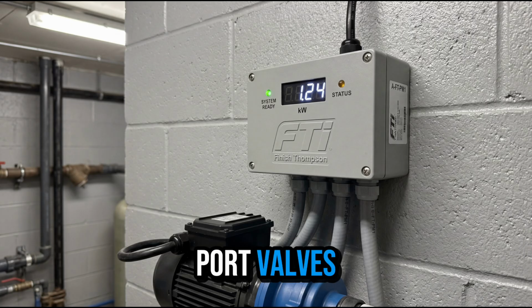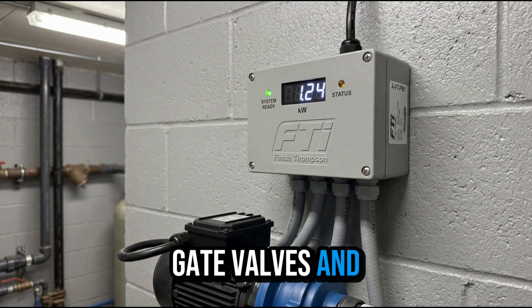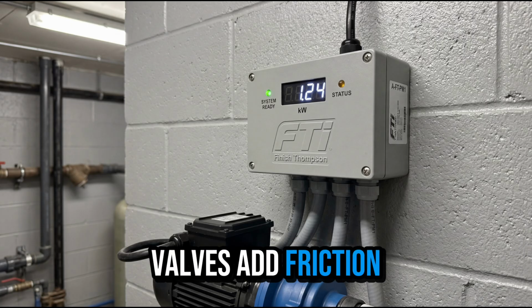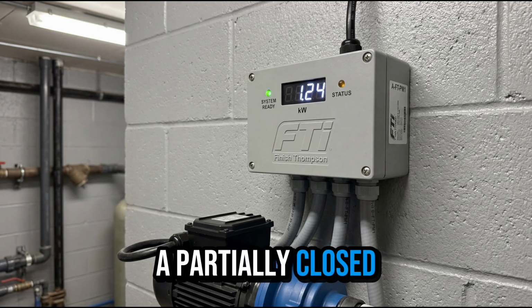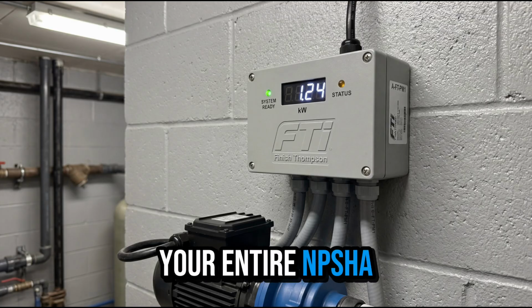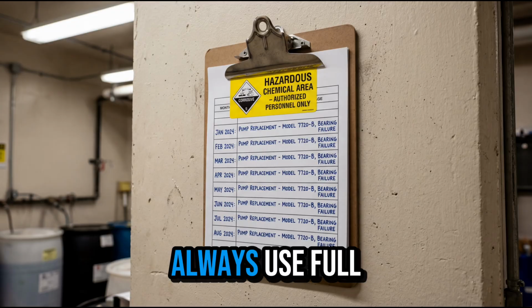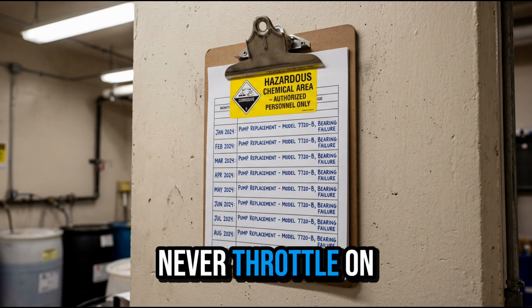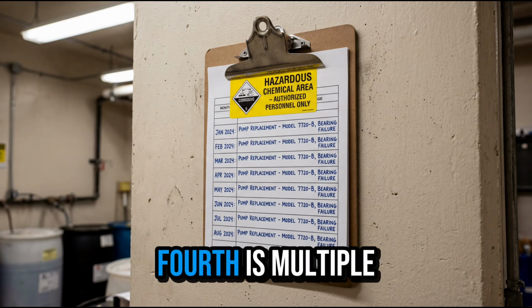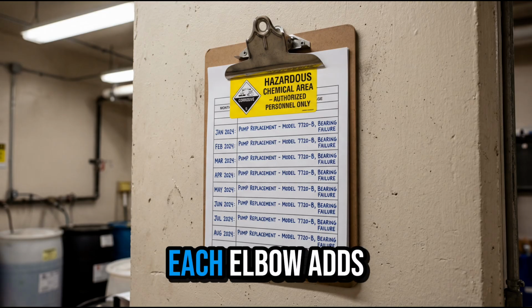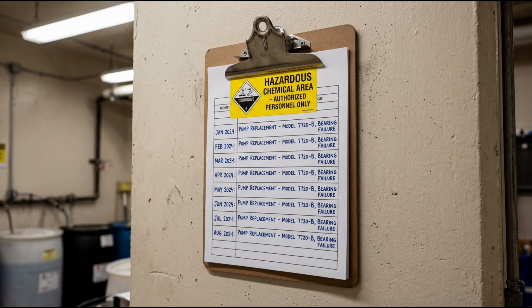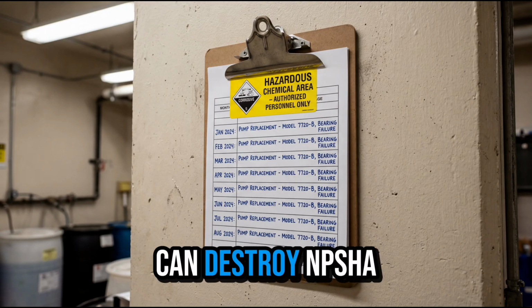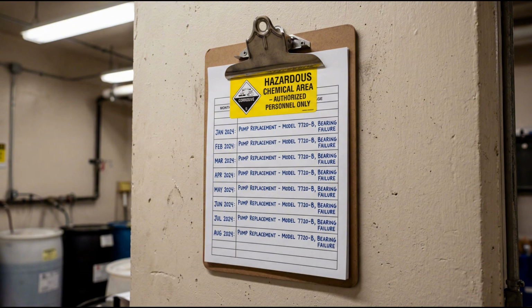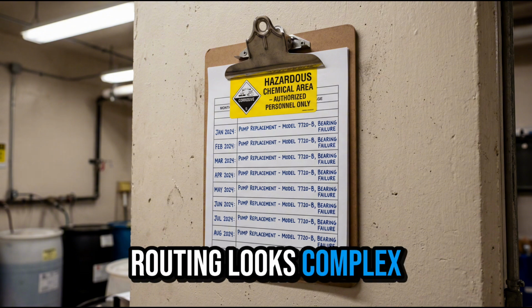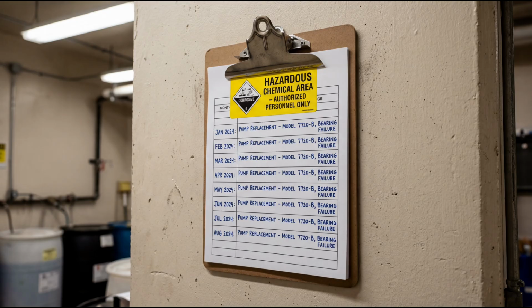Third is reduced port valves. Gate valves and reduced port ball valves add friction losses. A partially closed valve can eliminate your entire NPSHa margin. Always use full port valves and never throttle on the suction side. Fourth is multiple elbows. Each elbow adds pressure drop. 6 elbows in a short run can destroy NPSHa margin. If the suction routing looks complex, you likely have a friction loss issue.